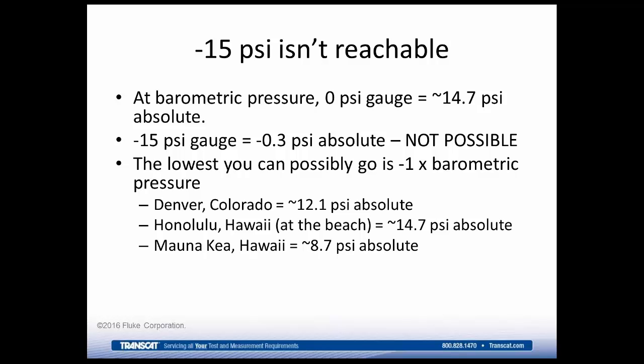So like Denver, Colorado, it's at a mile high, you're approximately 12.1 psi absolute. So the lowest you could possibly go in a perfectly leak-tight system with the most powerful vacuum pump is negative 12.1. Honolulu, Hawaii, right there at the beach, you're at sea level, you can get to negative 14.7. But if you climb to the top of that volcano, where you're much higher, in fact, you're more than a mile up, now your atmospheric pressure is only 8.7 psi absolute. So the lowest you can possibly go is negative 8.7.